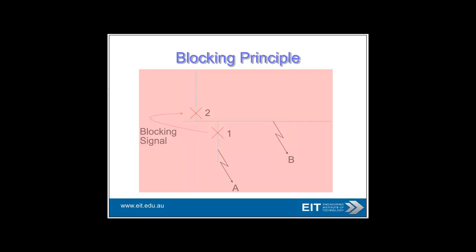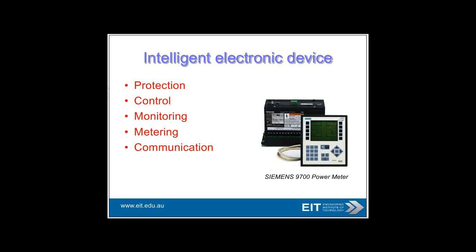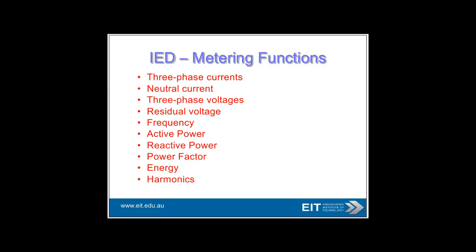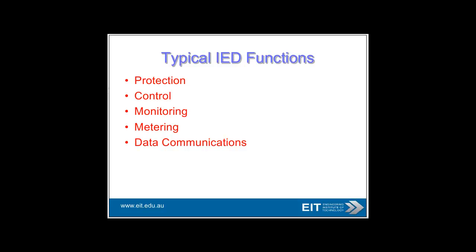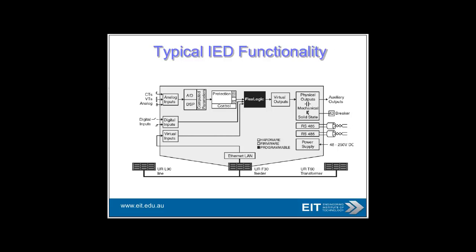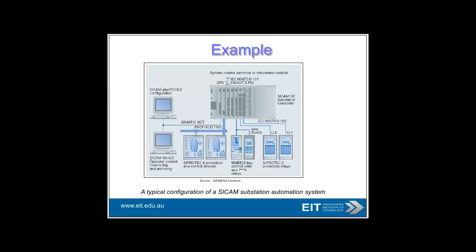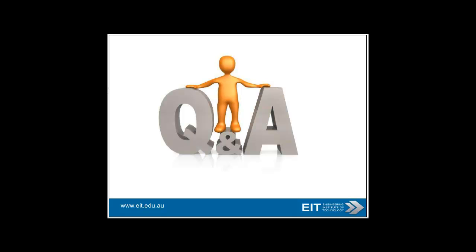All of this is digitized and you have to transfer this information using the IEC 61850 protocol. An IED handles protection, control, metering, monitoring, and data communications — it's basically a very intelligent RTU or PLC with a lot of overlap between different areas. Data is transferred to a SCADA system using the IEC 61850 protocol as the underpinning. That gives you a quick run through on IEC 61850 and some of the devices used to connect. Any questions, please shout — I'll be most gratified to answer them. Thank you very much.